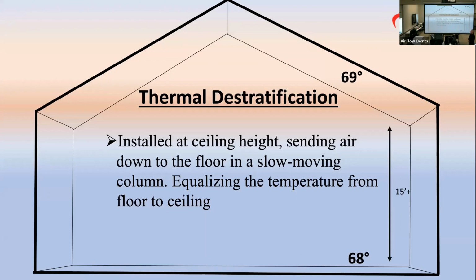So, thermal destratification. Destratification comes in installed at the ceiling height, sending air down to the floor in a slow moving column, equalizing the temperature from floor to ceiling. So instead of having 85, 90 degrees in the ceiling and 68 on the floor, you got almost an even temperature within the envelope that's going on, like you can see in the slide that we have here.